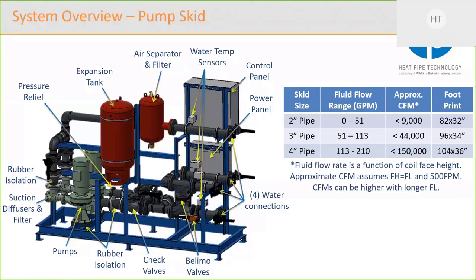Now, I also provided approximate CFM. The reason I say it's approximate is because I've made some assumptions. I've said your coils have the same fin height and fin length. Well, that's not entirely true. You could have a bigger fin height than fin length, or you could have a bigger fin length. What I'm really doing here is showing you an example of ballpark. This is the type of system you might use this skid on. And I've assumed 500 feet per minute, which is very reasonable, but sometimes on the high side when it comes to energy recovery. Obviously, the CFMs can be higher if you're using a longer face length because your square footage of your coil is bigger.